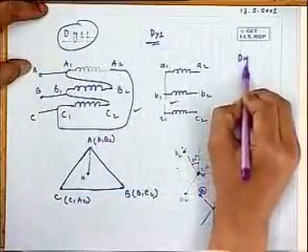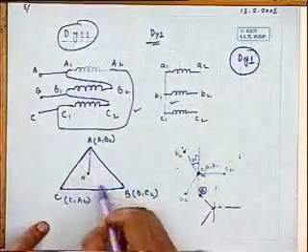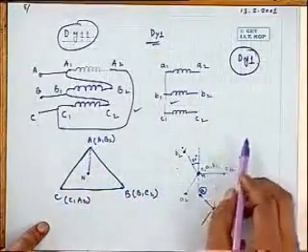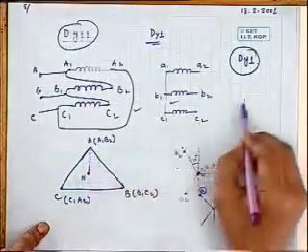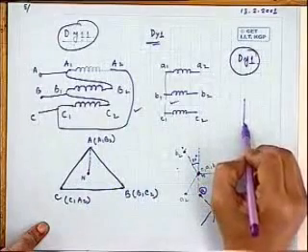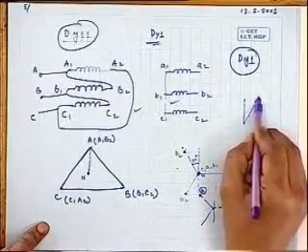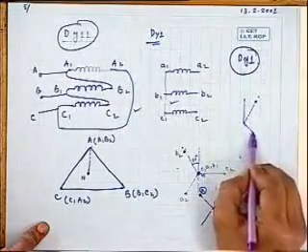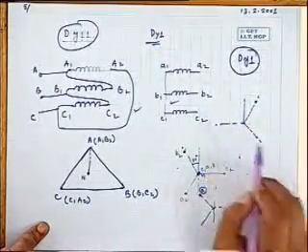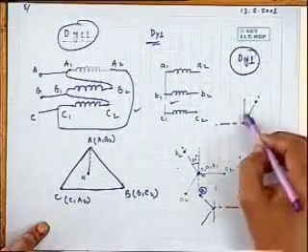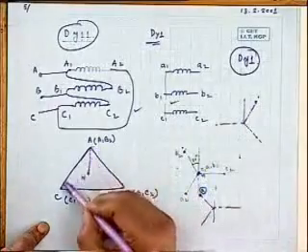This particular connection, whatever has been drawn, will be applicable to Dy1, is what I want to tell. Why? Because this is the primary voltage. So how will the secondary voltages look? I draw a parallel line to this phase voltage. Then the secondary voltage phase should be there. Here some A should come. Once this point is fixed, the other three lines I can immediately draw without any help. Is this voltage available?